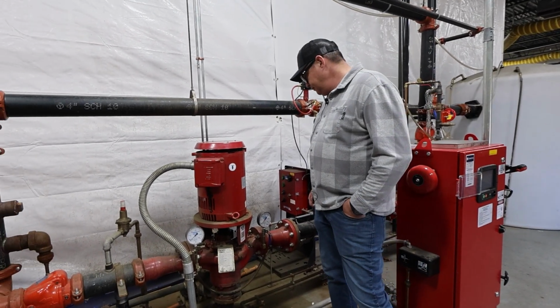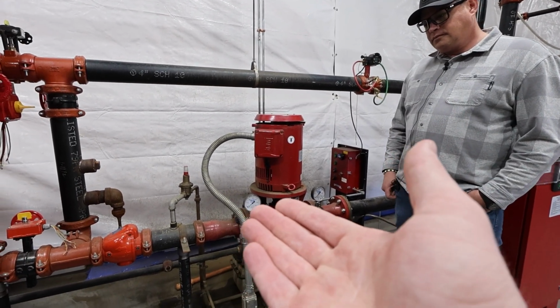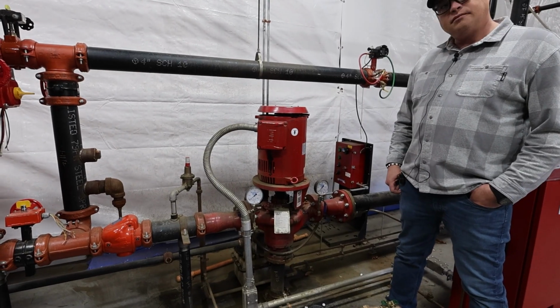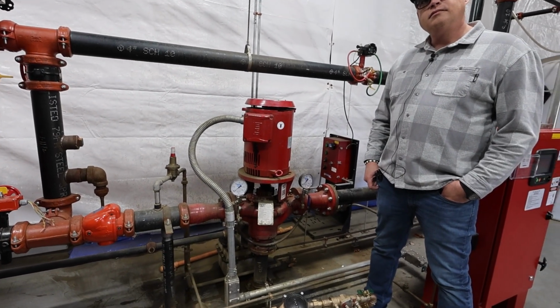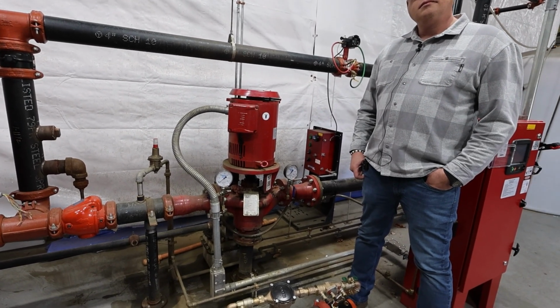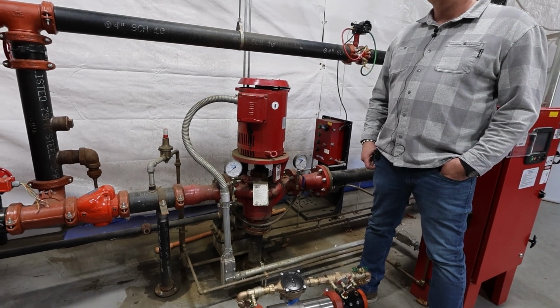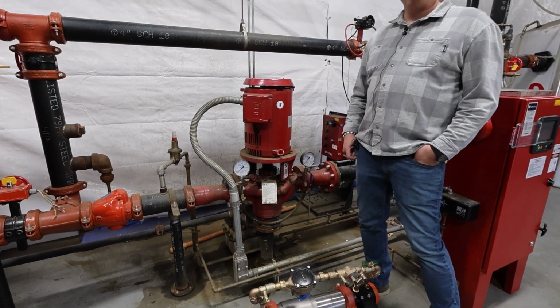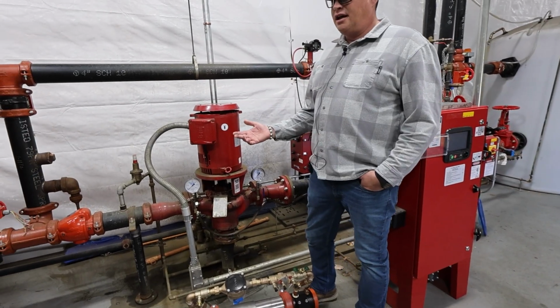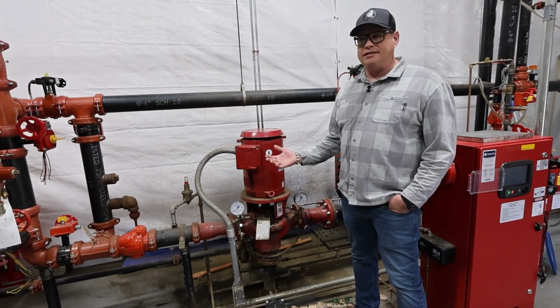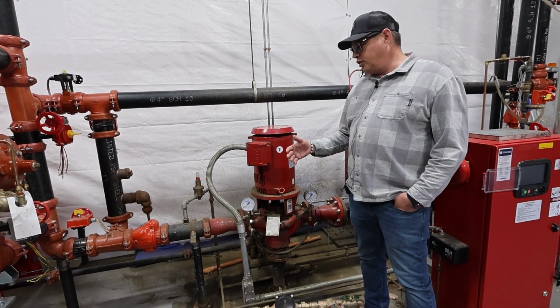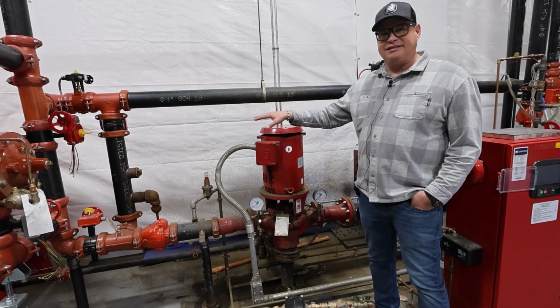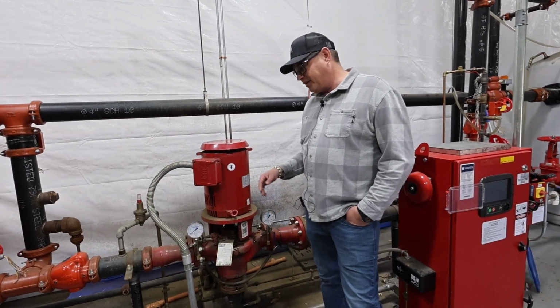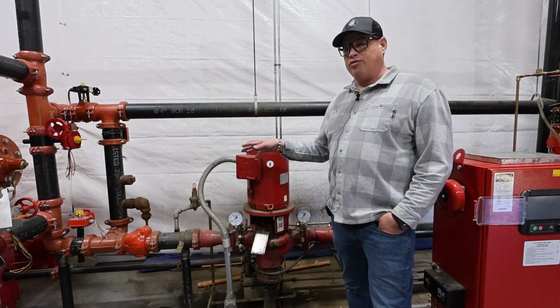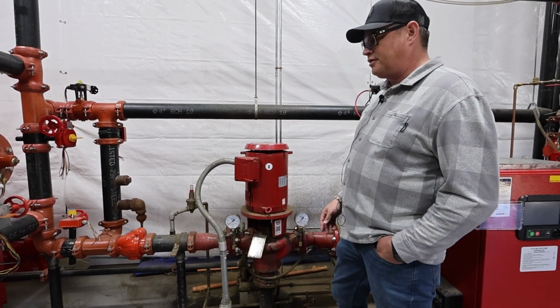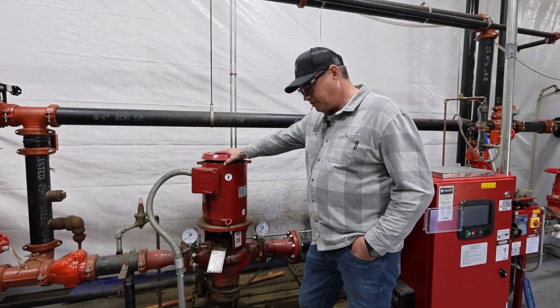The rule of thumb for sizing that is, not pressurized, but you want water. What I go by is the pipe size of the discharge, full of water, not pressurized shooting out, just dumping water. The main reason for that is during run tests the water gets hot, you need that dumping of excess pressure to help keep everything cool. If it's not flowing, it'll get really, really hot in the line and start cooking parts. Good for you guys, but bad for everybody else.